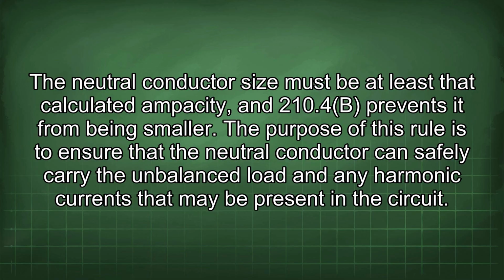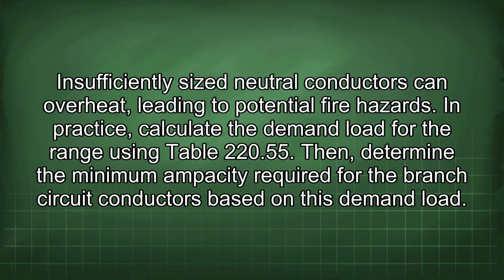The purpose of this rule is to ensure that the neutral conductor can safely carry the unbalanced load and any harmonic currents that may be present in the circuit. Insufficiently sized neutral conductors can overheat, leading to potential fire hazards.